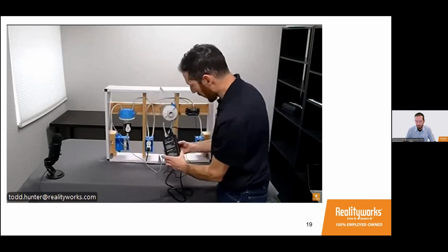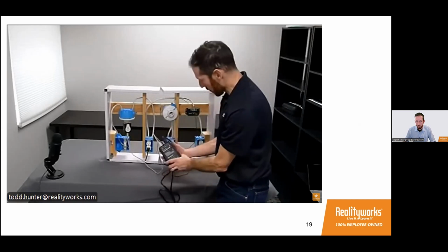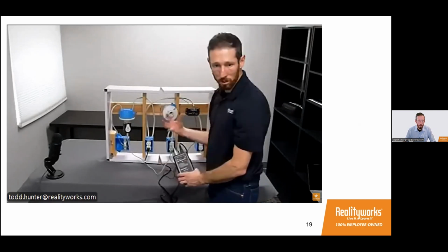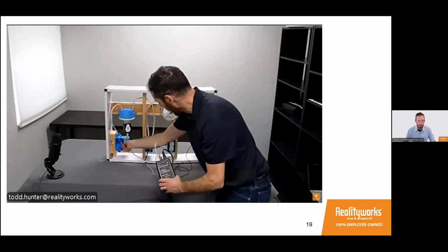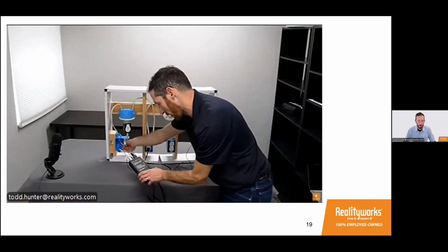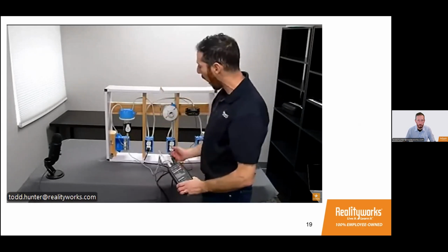and flip on the switch. Now, right away, I can see my outlet tester, which is evaluating this. It's giving me a code that says correct. However, my light socket tester, I got two signs that things are not working appropriately here. One, it's not lighting up. If I flip the switch, I'm not getting power. Right? But I can also see when I flip the switch that the code changes. And if I look at that, I get a hot neutral swapped.